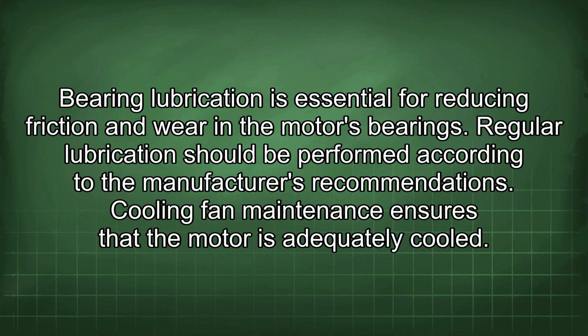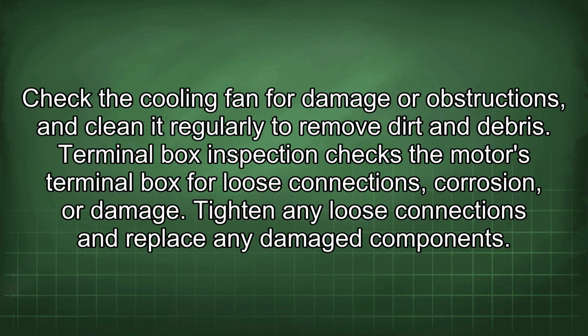Bearing lubrication is essential for reducing friction and wear in the motor's bearings. Regular lubrication should be performed according to the manufacturer's recommendations. Cooling fan maintenance ensures that the motor is adequately cooled. Check the cooling fan for damage or obstructions, and clean it regularly to remove dirt and debris.